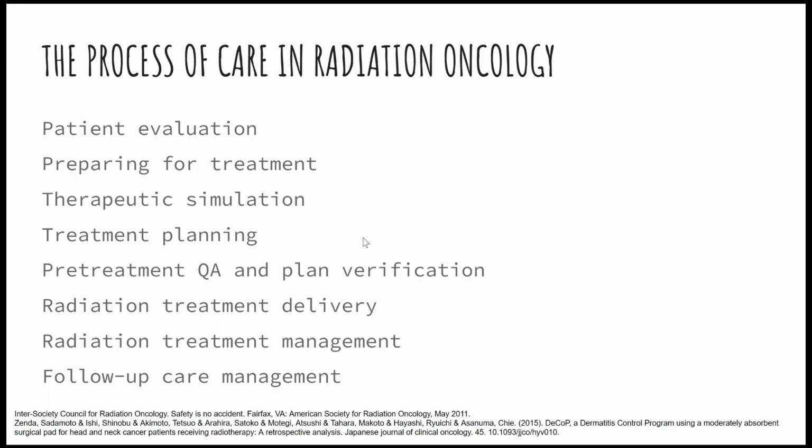After that, we do a pre-treatment quality assessment and a plan verification. This is basically after the plan has been approved, we check whether the machine would be able to deliver the exact same plan or not.